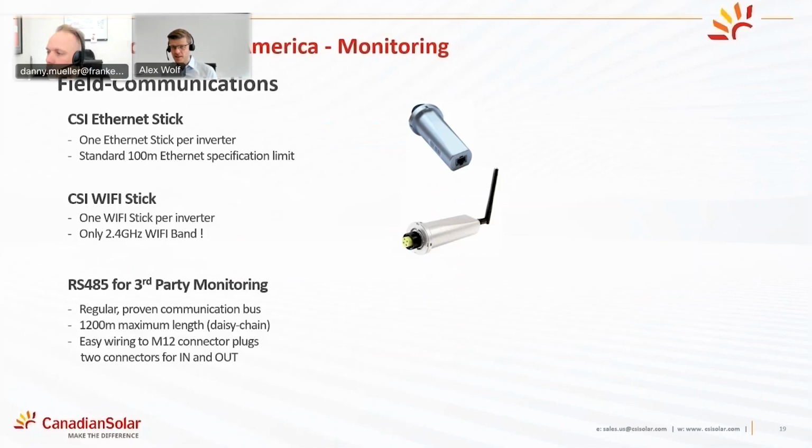When it comes to monitoring, there are quite a few options available with the inverter. Going to the bottom row right away, you can have a conventional old-fashioned RS485 daisy chain from one inverter to the other. It's a very reliable two-wire twisted pair communication, and you can use that, for example, with any third-party monitoring. The communication on the Modbus RTU is SunSpec compliant, so any third-party manufacturer for monitoring systems can use that protocol and can be implemented with that CSI inverter.